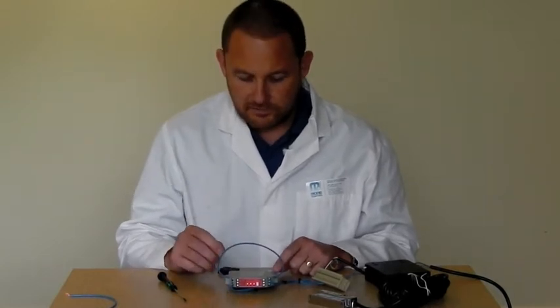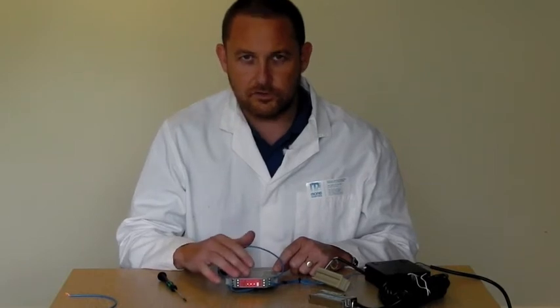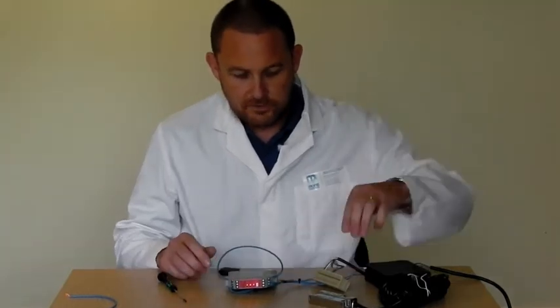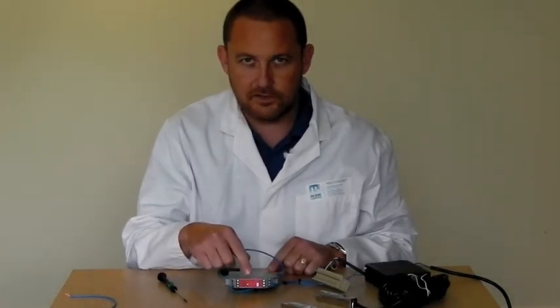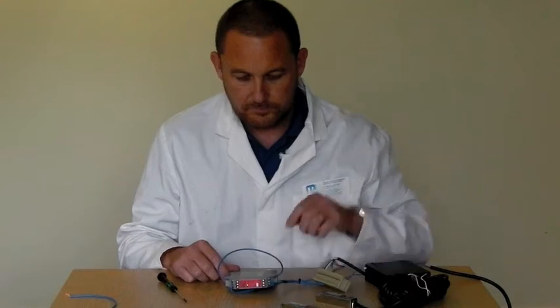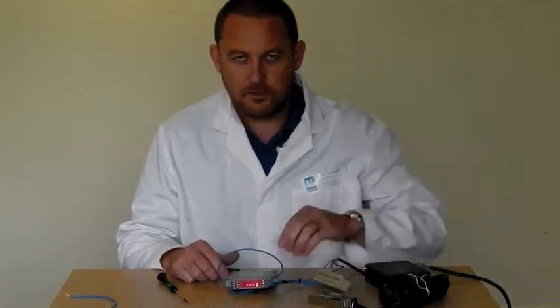So with the auto-reset, the safety relay is constantly trying to reset itself. If we open a door, you'll see that the LEDs have gone off, indicating the safety circuit has been broken. Close the door, both channels of the safety relay come in.